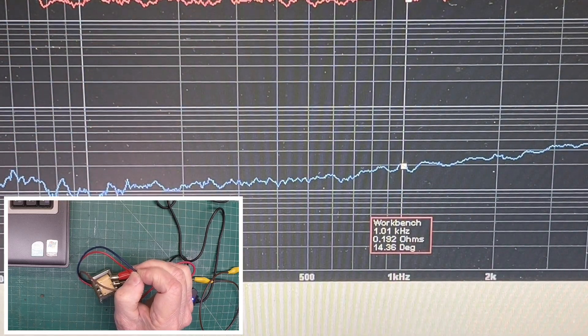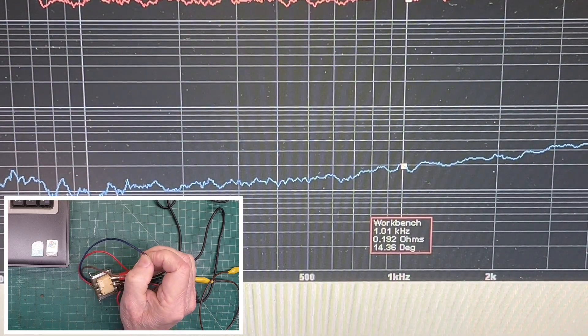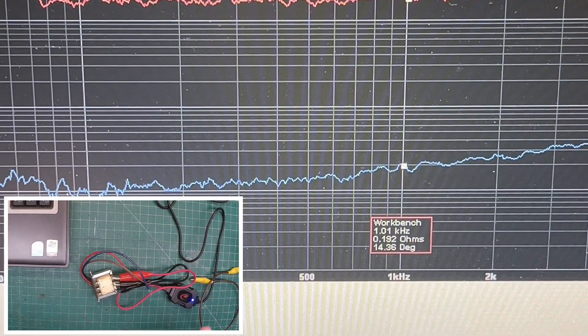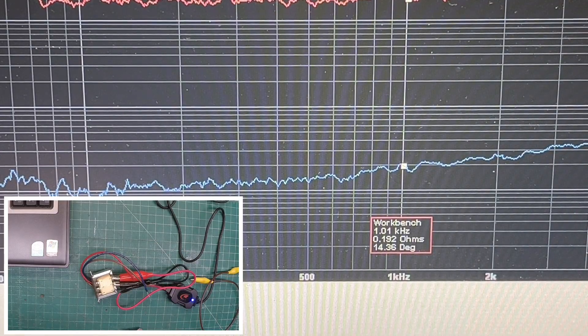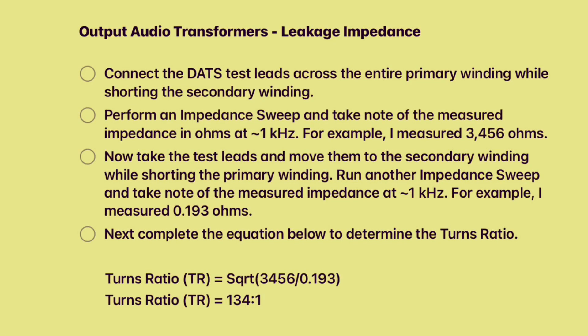We'll take note of that number as well — 0.192 ohms. And we'll refer back again to my notes from the previous measurement. As you can see, we'll take the square root of the first measurement I made, divide that by the second measurement, and that will give us the turns ratio for the output transformer for that particular tap location.